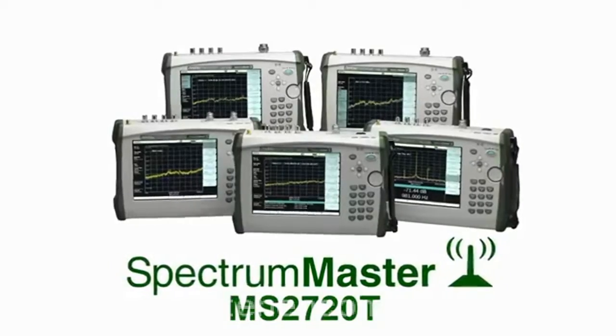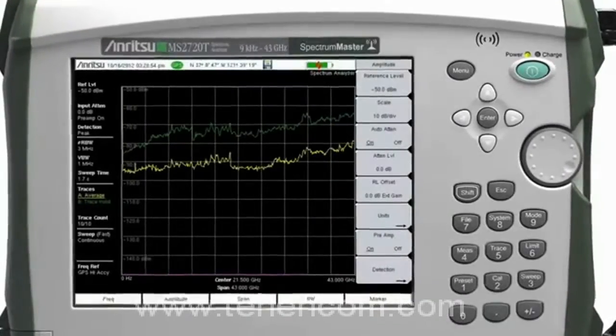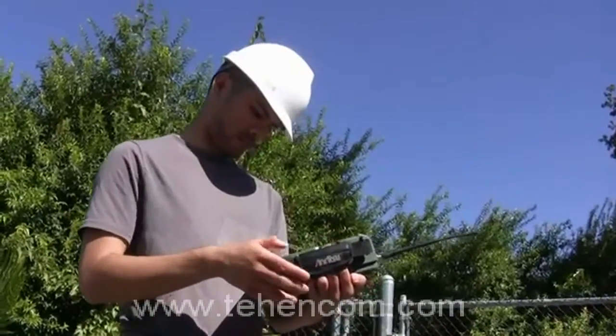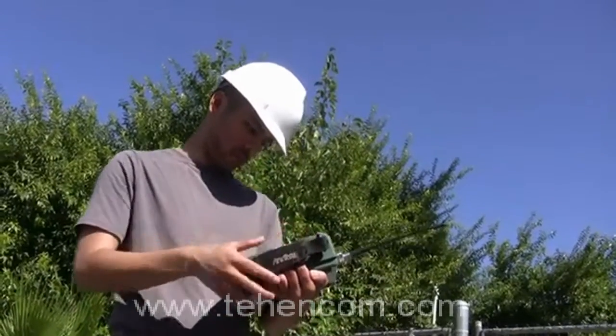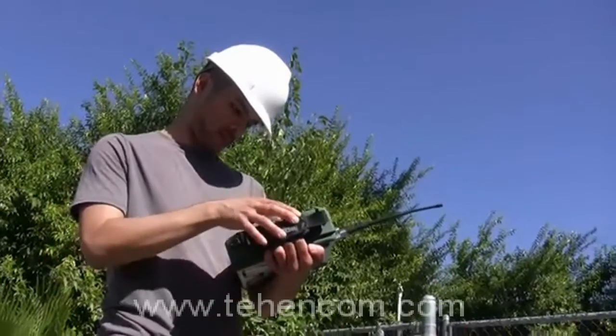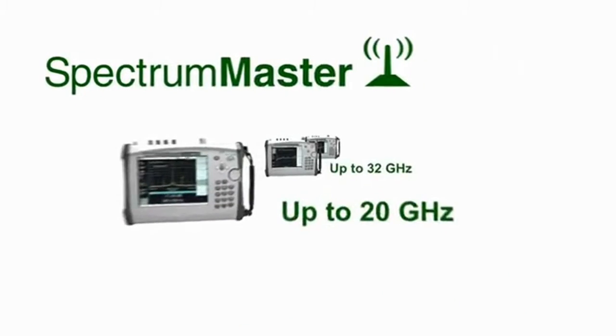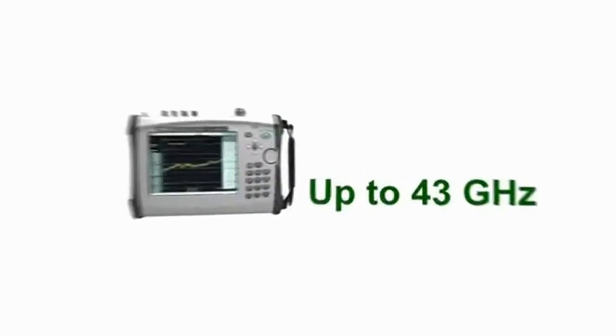The new Spectrum Master MS2720T instruments include a broadband pre-amplifier that operates all the way to 43 GHz, providing unprecedented sensitivity needed for interference hunting. The frequency coverage of all models starts at 9 kHz and extends to 9 GHz, 13 GHz, 20 GHz, 32 GHz, and 43 GHz.